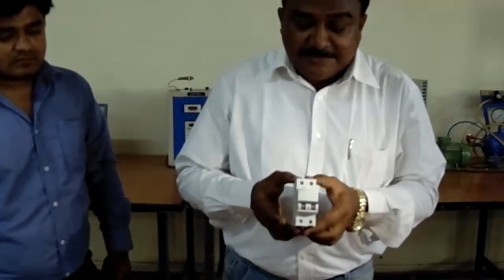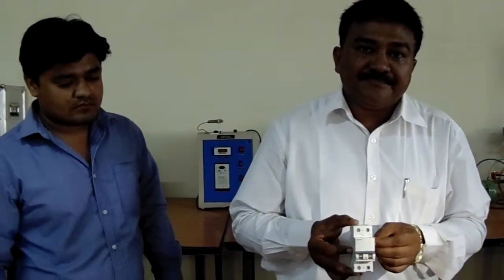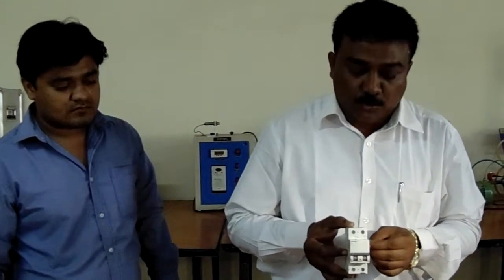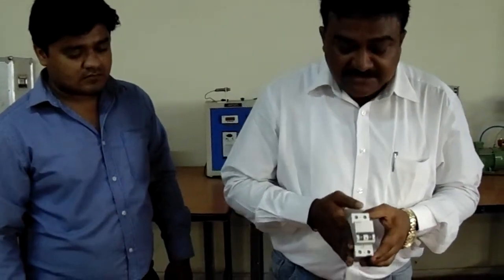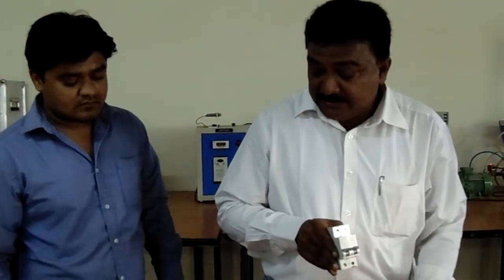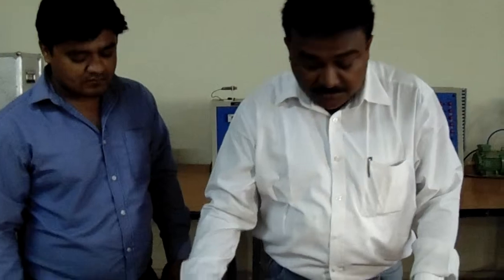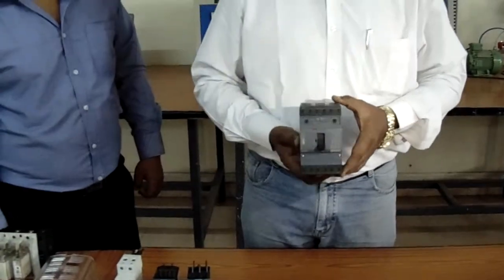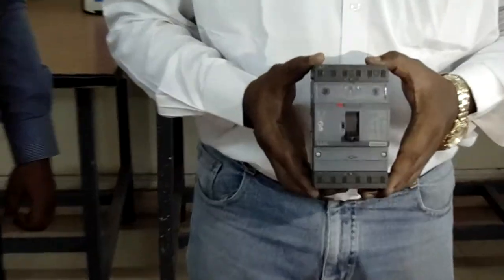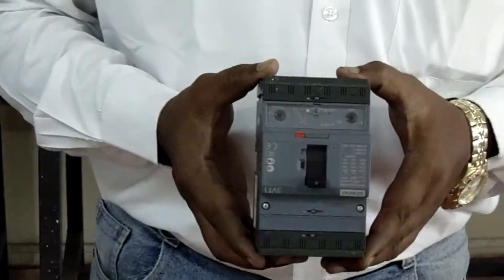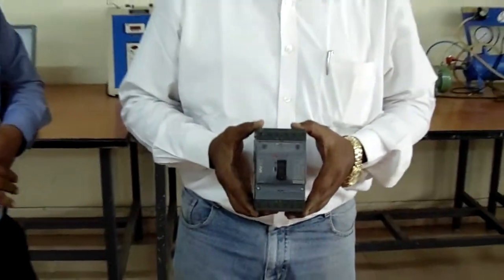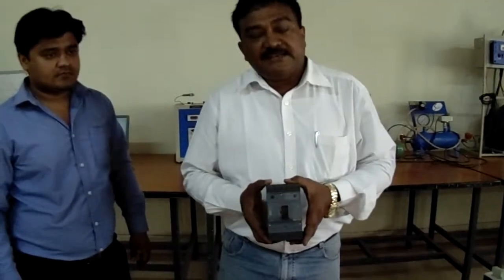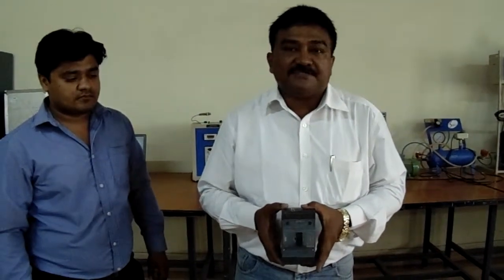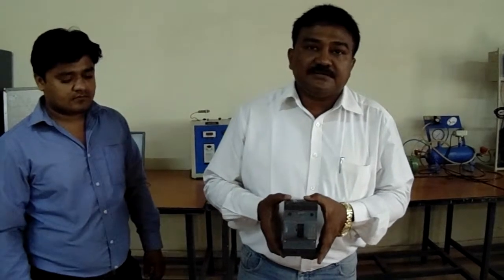Now, these miniature circuit breakers are also available in single pole, double pole, single pole neutral, 3-pole neutral, and 4-pole. Above 63 amperes, industry normally uses MCCBs. MCCB is a molded case circuit breaker. These molded case circuit breakers are used up to 800 amperes normally. This again can be used for single phase, double phase, 3-phase, and is also available in 4-pole.